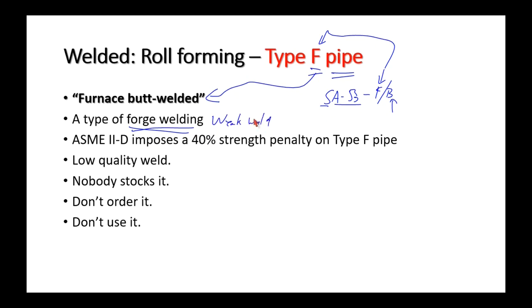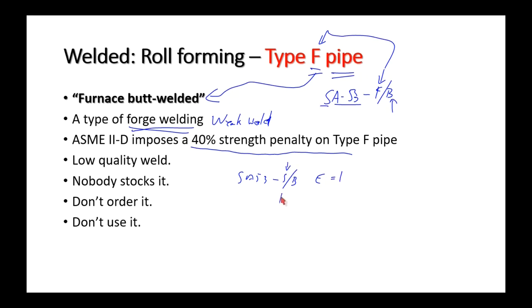ASME has never banned furnace butt welded pipe, but they impose a 40% strength penalty. So SA-53 S/B seamless has a longitudinal joint efficiency E of 1, but SA-53 Grade F/B has a longitudinal joint efficiency of only 60%. This material is considered only 60% as strong as seamless.